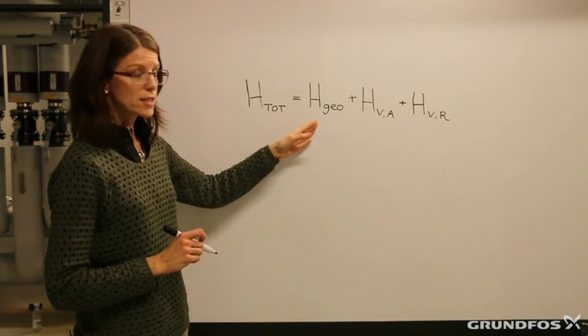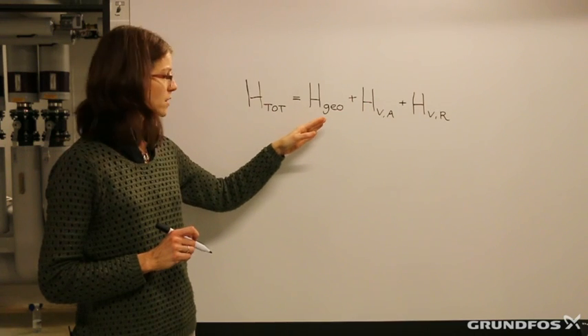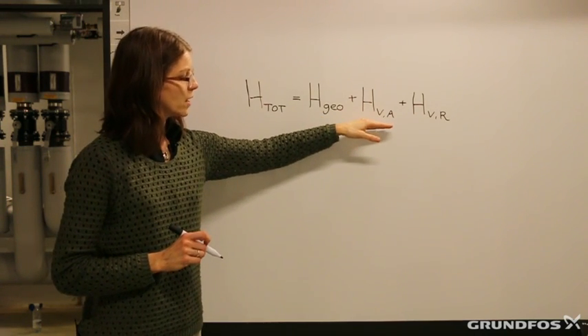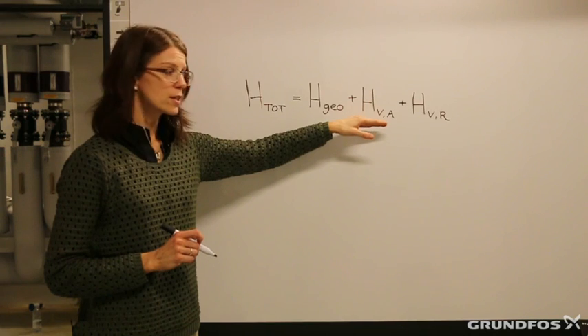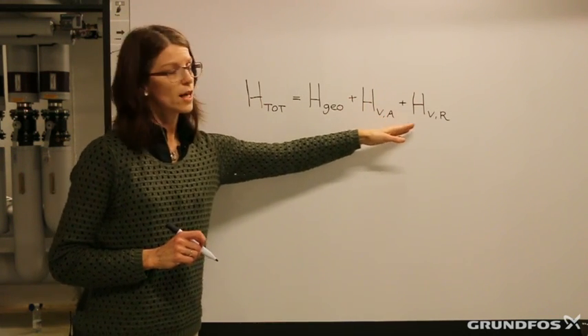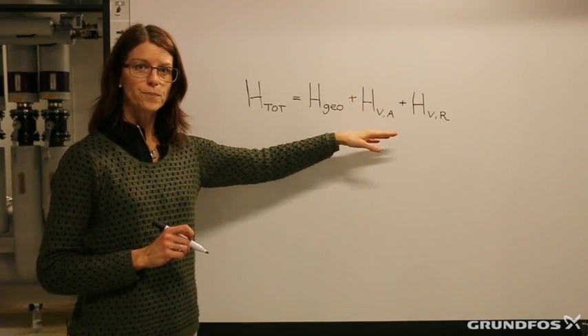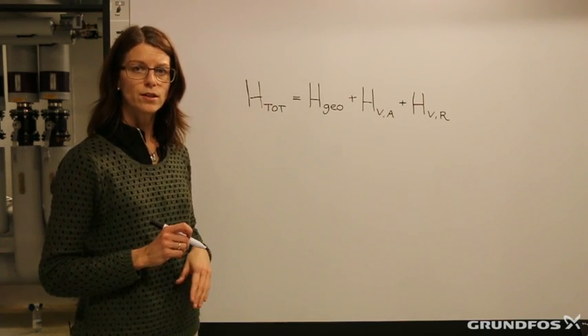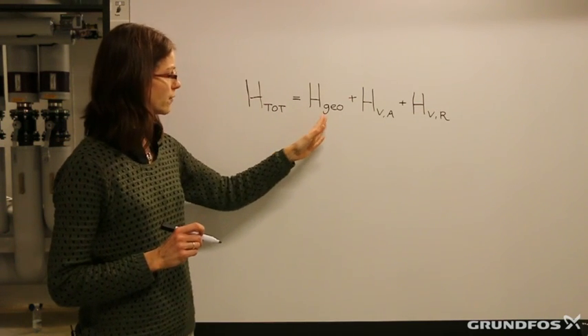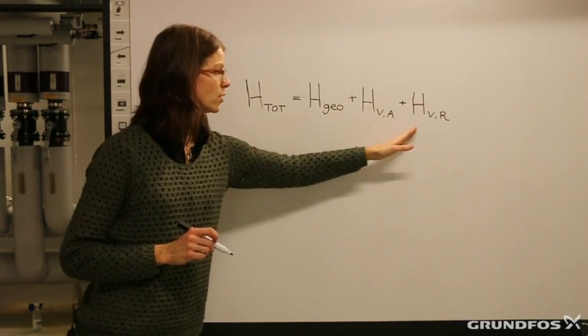The geodetic height is independent of the flow rate in the system — it's a constant — whereas the friction loss in the fittings, valves, and linear pipe is a dynamic value. It depends on the flow in the system. So we have a static value and we have a dynamic value.